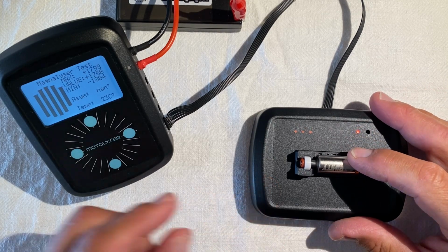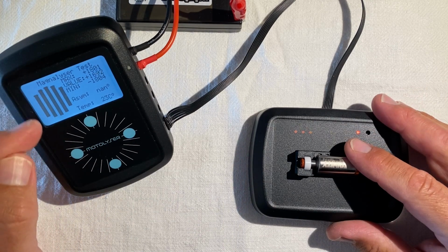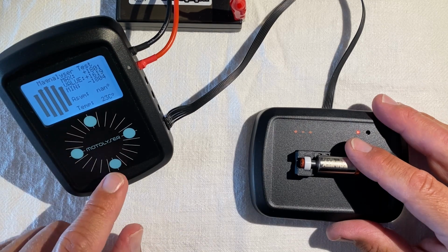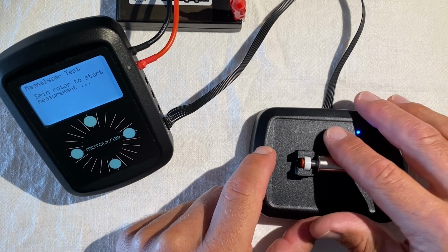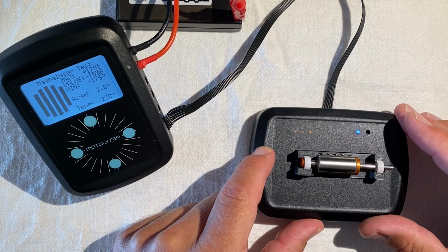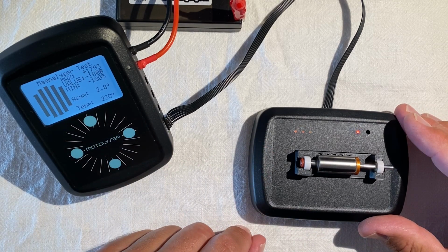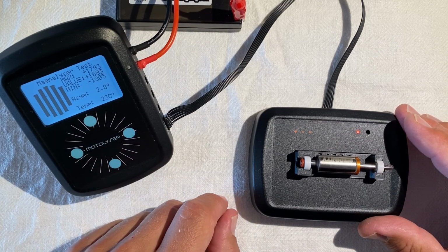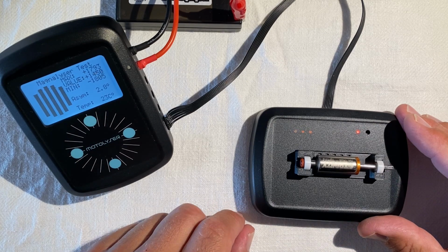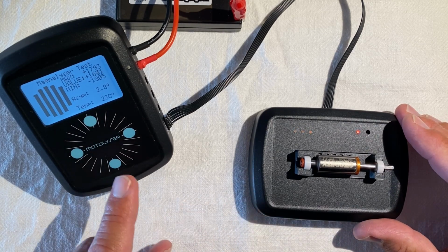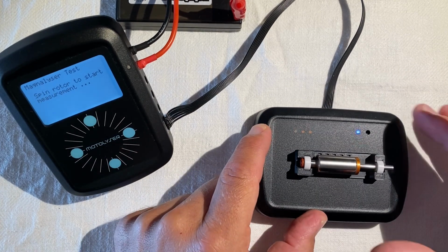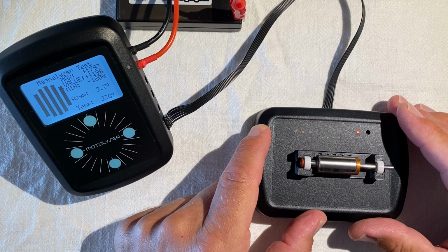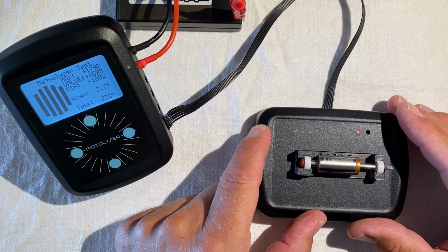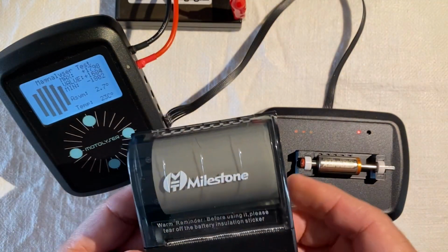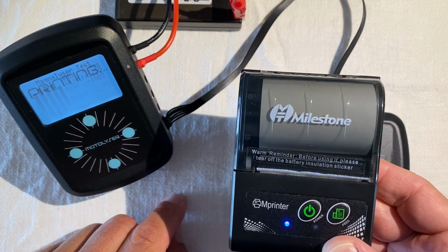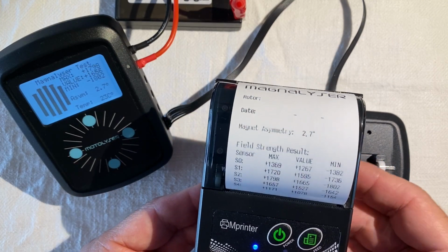When that's done, we can see our readings coming from the sensors. To make sure you have a clean reading, you should start the test by hitting the down button and then just spin it once and wait, and then the results come up. So these are the clean results. You see the asymmetry, 2.8 degrees. You have the max and the mean values around 1800. And if you want to make another test, you just hit the down button again, and then you're good to go. If you want the printout of this, you can bring out your Magnalyser printer, turn it on, and hit the right button, and then you'll get the readings right out. Like that.